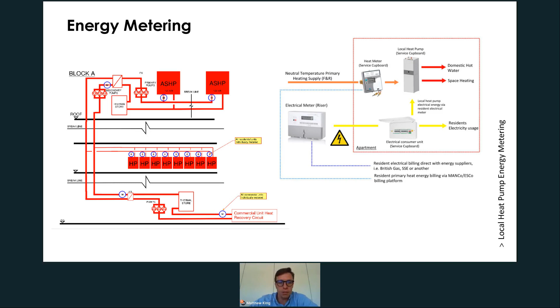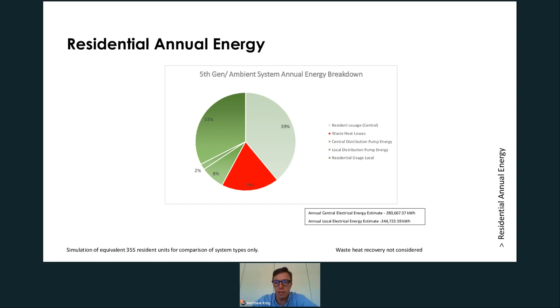The relatively high waste heat loss of the fifth generation network was one consideration we had early on when looking at this. The aspect of this is that it's after the meter, so there are a lot of standing losses in the domestic hot water storage vessels, and that can exacerbate things like internal overheating in residential units. That's a key consideration. But also commercially, compared to a fourth generation network, you're not losing it from your side of the meter - so that isn't your cost as an ESCO or network operator, it's after the meter. That de-risks it slightly, but it's still a significant cost to be considered when looking at these network designs.